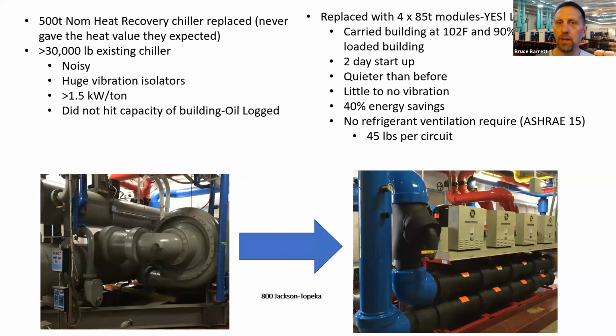That machine, when we watched it run on the hottest day of the year in a full load building, 102 outside, 90% humidity, hot Kansas day, 1.5 kW per ton, real. Terribly, terribly inefficient. That machine weighed about 30,000 pounds. Every time the compressor turned over, it would shake the entire floor of the building. It was replaced with 4 85-ton modules.